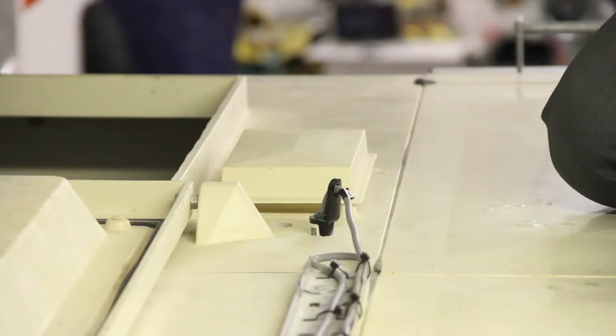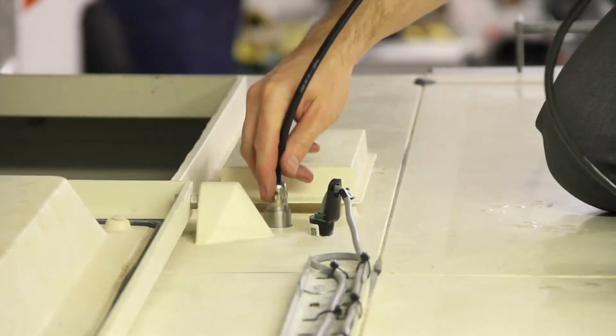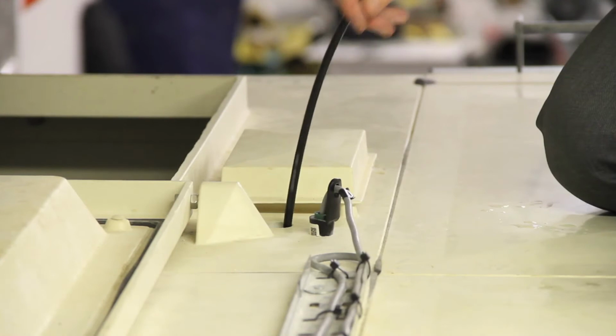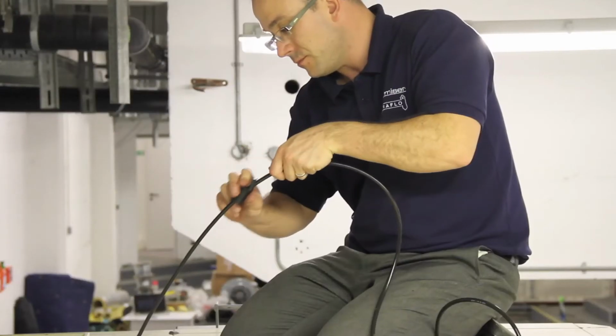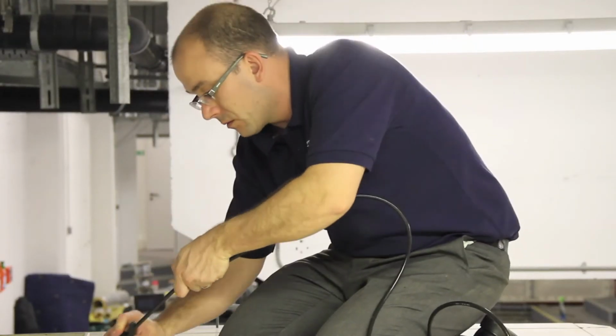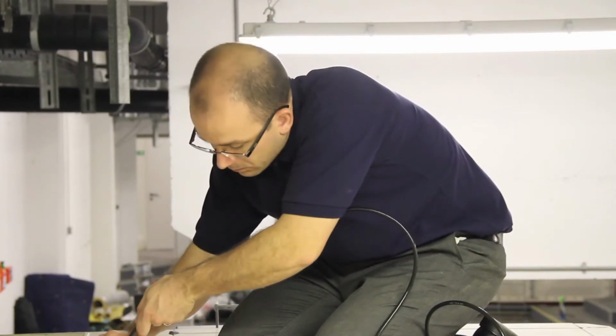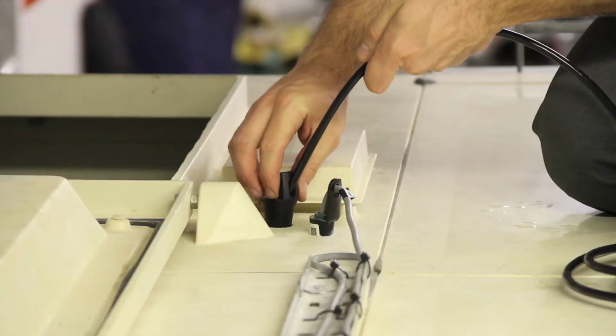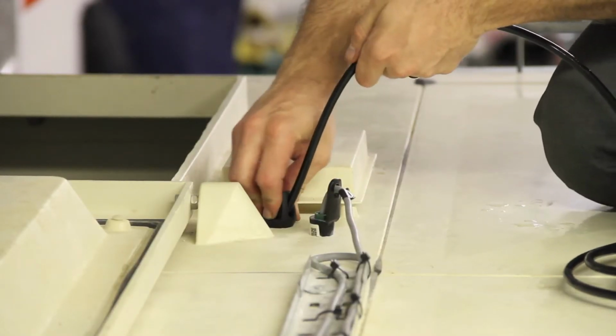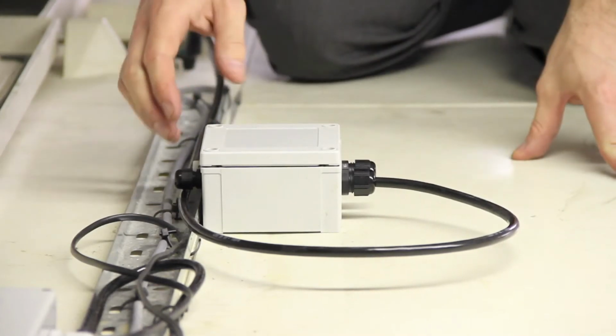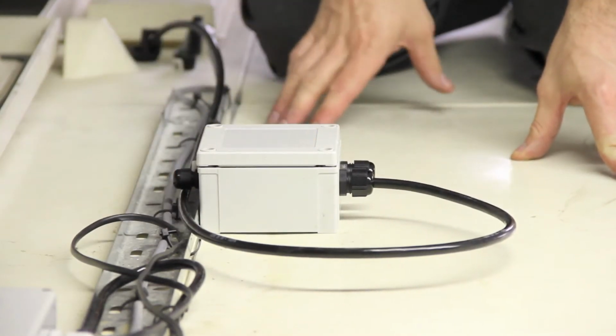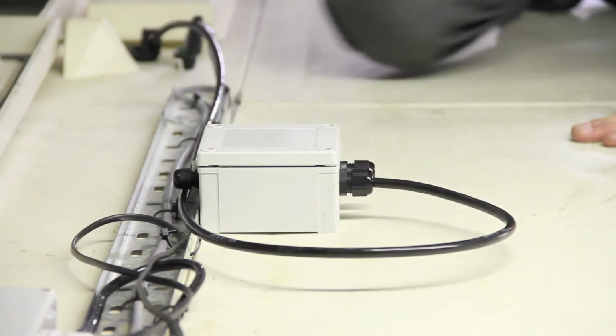Decide where the hole needs to be drilled, drill a 25mm hole, taking care to prevent debris falling into the tank, and drop the sensor into the tank all the way to the bottom, leaving the sensor just touching the bottom of the tank in a vertical orientation. Then coil any excess cable around the vent box and fix it to the top of the tank using the sticky feet provided.